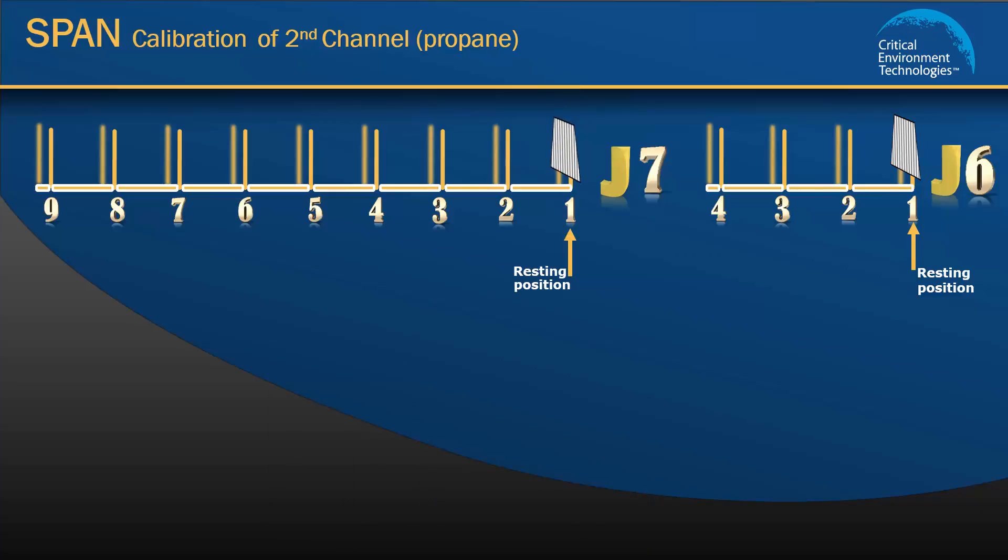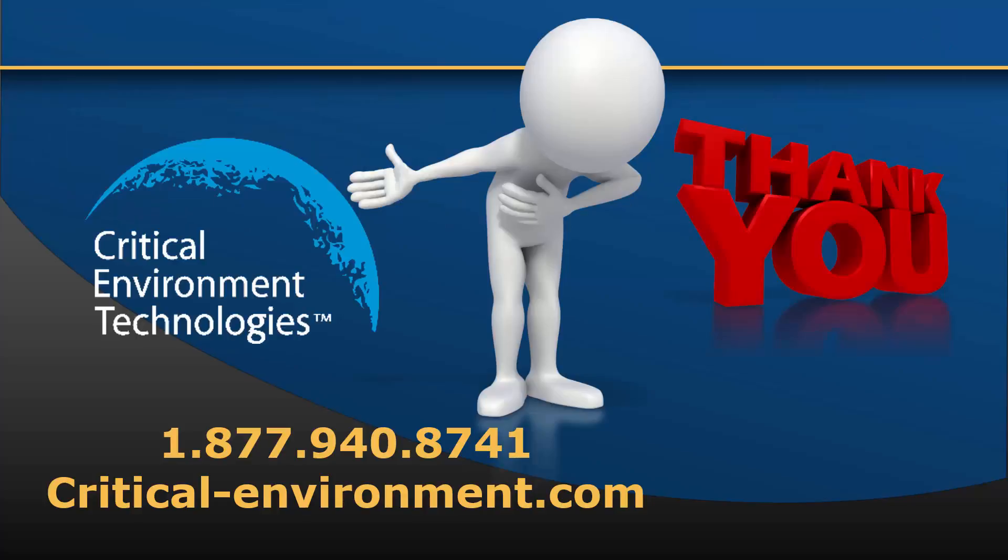This completes the calibration procedure for channel 1 and channel 2 of the Gem type D. Best practice after calibration is to do a bump test for both sensors to make sure the gas readings are accurate and the sensors have been calibrated properly. If you would like more information or in-depth training, you can sign up to take our service training courses. Please visit us at critical-environment.com or call 1-877-940-8741. Thanks for watching.